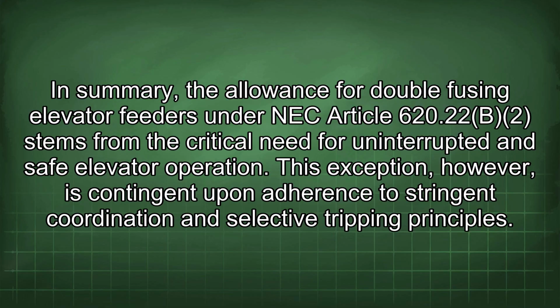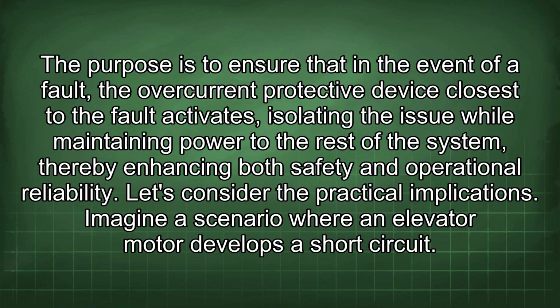In summary, the allowance for double fusing elevator feeders under NEC Article 620.22(B)(2) stems from the critical need for uninterrupted and safe elevator operation. This exception, however, is contingent upon adherence to stringent coordination and selective tripping principles. The purpose is to ensure that in the event of a fault, the overcurrent protective device closest to the fault activates, isolating the issue while maintaining power to the rest of the system, thereby enhancing both safety and operational reliability.